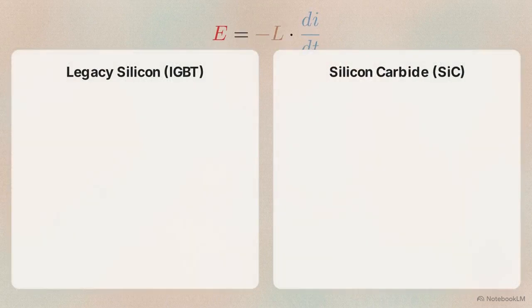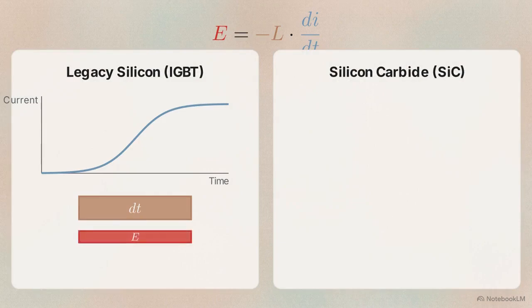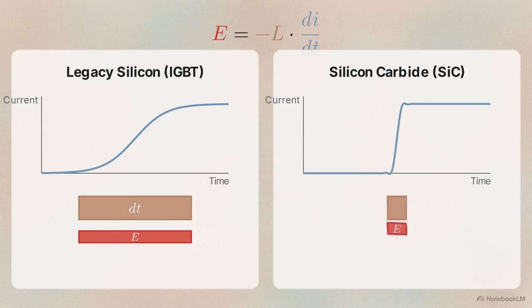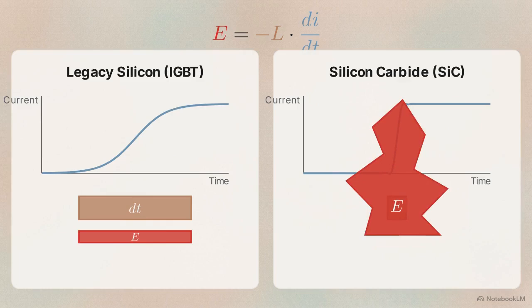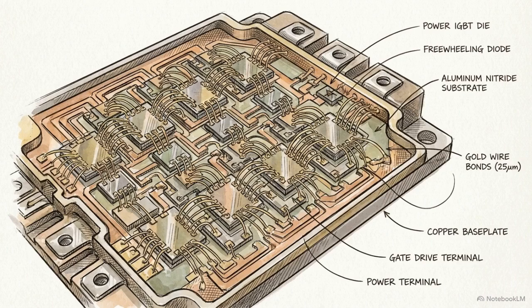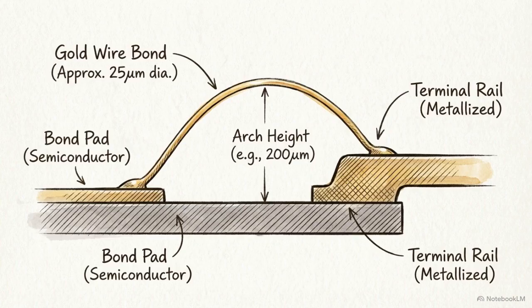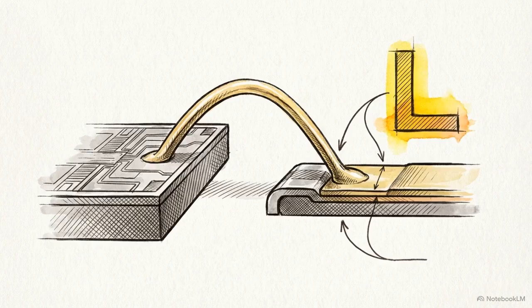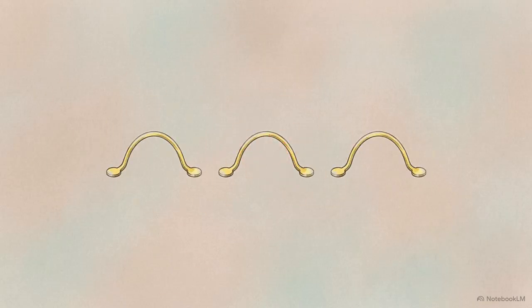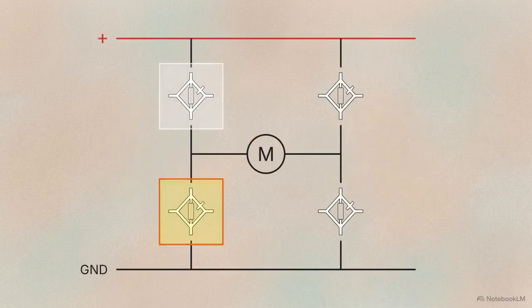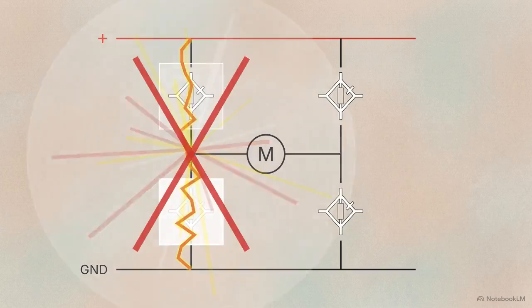Faster current changes cause larger spikes. Legacy silicon IGBTs switch slowly, meaning dt is large, keeping the voltage spike small. But silicon carbide switches 10 times faster, shrinking dt. Dividing by this tiny number causes E to violently expand, generating a massive destructive spike. This abstract math has immediate physical consequences inside a semiconductor module. The L in the formula, the physical inductance, comes from the microscopic wire bonds used to connect the silicon chips to the module housing. The massive voltage spikes generated across these tiny wires induce phantom signals. This creates crosstalk, which forces neighboring transistors in the bridge circuit to turn on unpredictably, creating catastrophic short circuits.